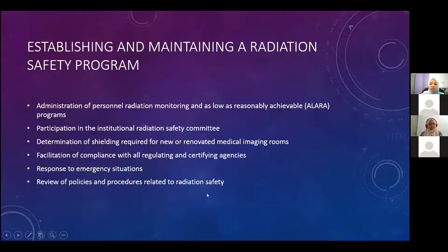The determination of shielding required for new or renovated medical imaging rooms. They should specify shielding for an X-ray facility using diagnostic X-ray imaging systems, design satisfactory radiation shielding for all types of diagnostic radiology equipment, and assess the effectiveness of the shielding. This picture shows the physicists measuring the scattered radiation outside the X-ray room to ensure the shielding is adequate, and this picture is the scattered radiation measurement at the console area in the mammography room where the radiographer stands behind.